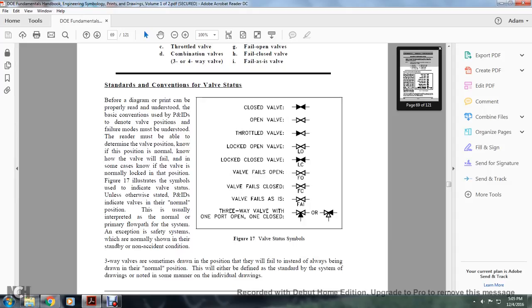Three-way valves are sometimes drawn in the position they will fail to instead of always being drawn in their normal position. For a closed valve, you have a fully-colored closed butterfly valve symbol. An open valve is a non-colored butterfly valve. A throttle valve is a half-colored butterfly valve. A locked open valve is a butterfly valve with LO. A locked closed valve is a fully-colored butterfly valve with LC. A fail-open valve is a butterfly valve with FO. A fail-closed valve is a butterfly valve with FC. A fail-as-is valve shows FAI. A three-way valve is open with one port open and one port closed, shown as one of the butterfly segments in the three-way cross filled in to indicate direction.